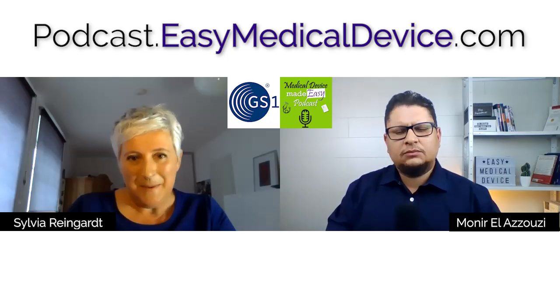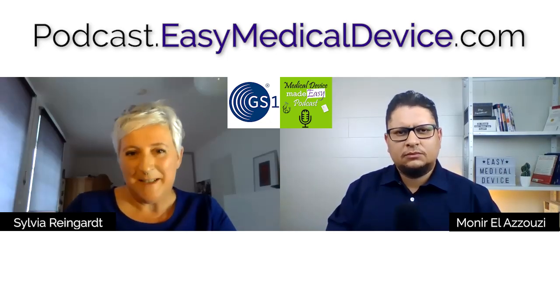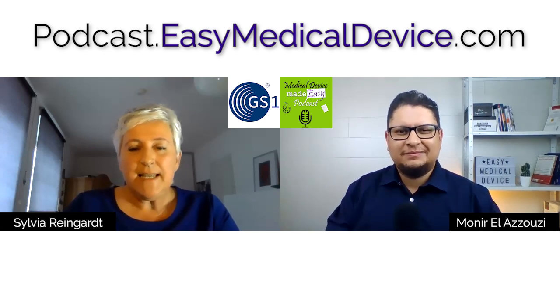So for those working with GS1 standards, they can use the GS1 identifier called Global Trade Item Number. We use the abbreviation GTIN. So the GTIN is equivalent to the UDI-DI. With the GTIN, you can comply with those requirements around UDI-DI.